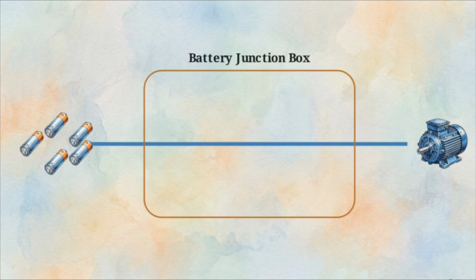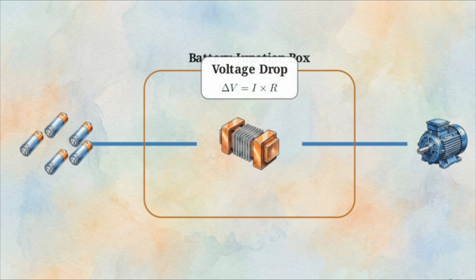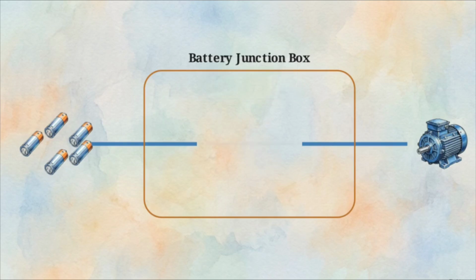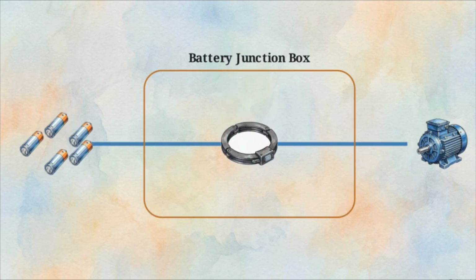This vector diagram illustrates one method for measuring this, placing a shunt resistor directly in line with the main high-voltage wire path. Because the shunt has a precisely known electrical resistance, measuring the slight voltage drop across it calculates total current. An alternative method relies on non-contact Hall effect sensors. Instead of an inline resistor, a sensor ring simply clamps around the exterior of the cable.